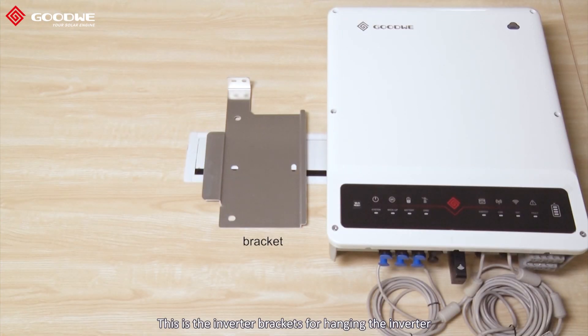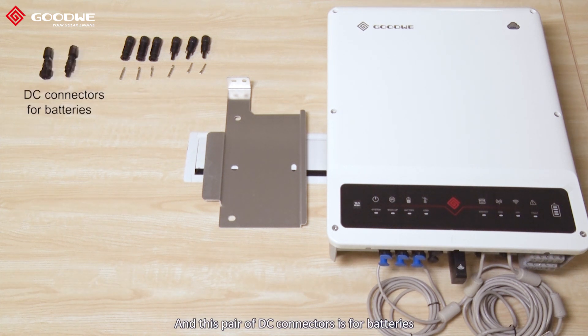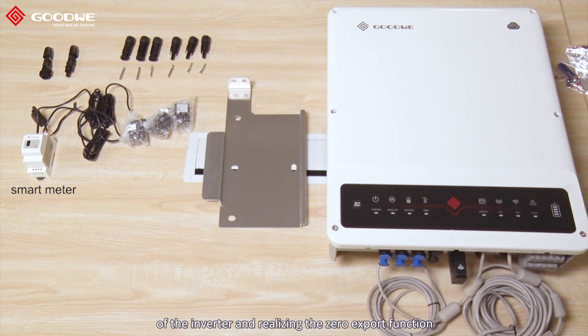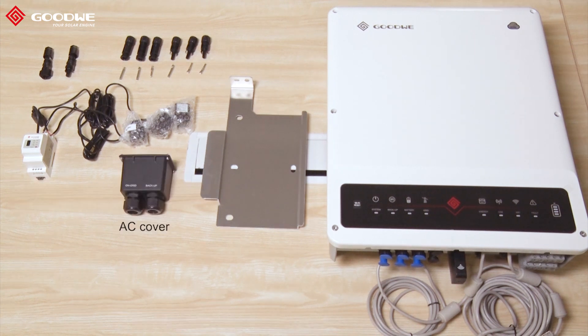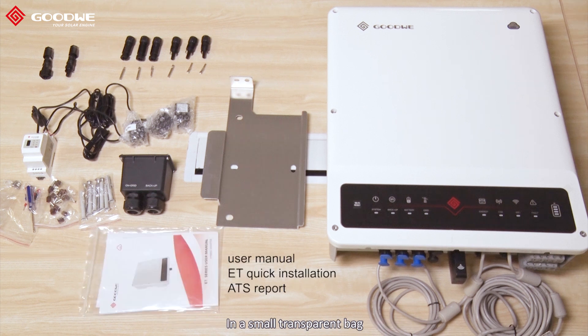This is the inverter bracket for hanging the inverter. Here we have DC connectors for PV panels, and this pair of DC connectors is for batteries. Here we have the smart meter for controlling the output of the inverter and realizing the zero export function. It's already connected with three CTs and they're all pre-wired. This is the AC cover for realizing IP65 protection. For installing the inverter we have all the necessary screws and screwdriver. In the small transparent bag we have the smart meter user manual, the ET inverter user manual, and the ET quick installation and ATS report.